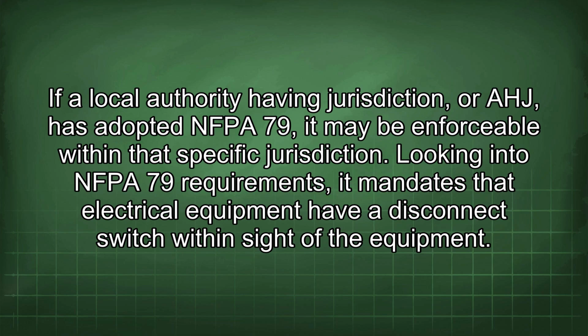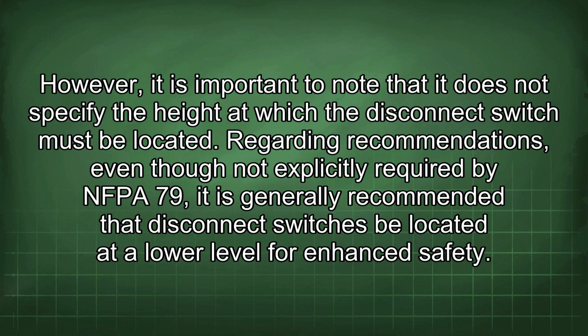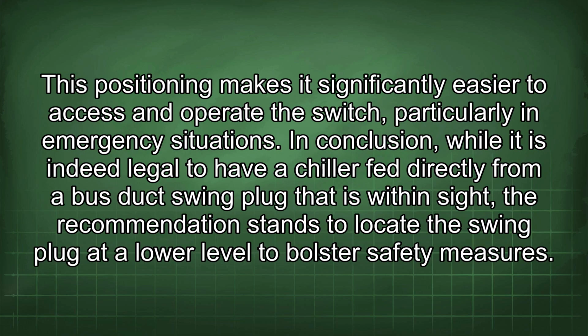Looking into NFPA 79 requirements, it mandates that electrical equipment have a disconnect switch within sight of the equipment. However, it does not specify the height at which the disconnect switch must be located. Regarding recommendations, even though not explicitly required by NFPA 79, it is generally recommended that disconnect switches be located at a lower level for enhanced safety. This positioning makes it significantly easier to access and operate the switch, particularly in emergency situations.